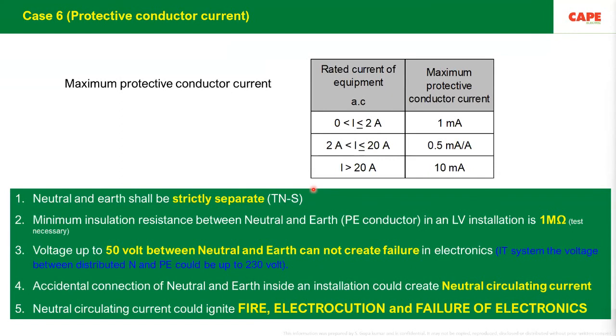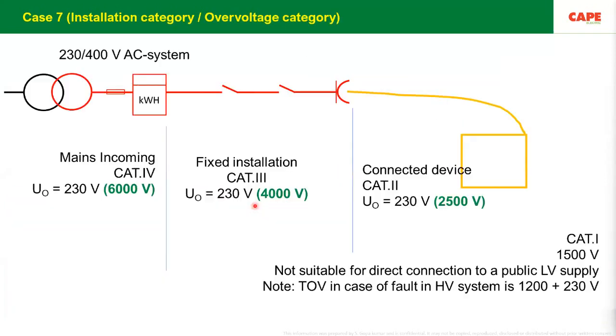They were using a device called, again a black box, I forget the name, a digital earthing system. This particular device says that you don't need to earth your electrical apparatus, and that system was creating a hell of a lot of leakage current, and this was the reason for the arc. So with electrical safety, please understand that you don't have any shortcuts. You have to follow the books, you have to follow the science, and only the scientific way of protective measures must be installed or followed.